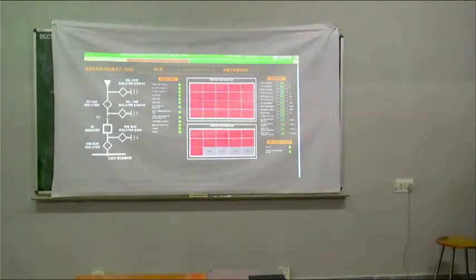So all this protection data is coming from our protection relays. How does this relay communicate? It communicates using an RJ45 cable to my gateway. In that RJ45 cable, it has to communicate in one language - the language can be Modbus, or it can be IEC 61850. Using that, we are going to read the data into our gateway.